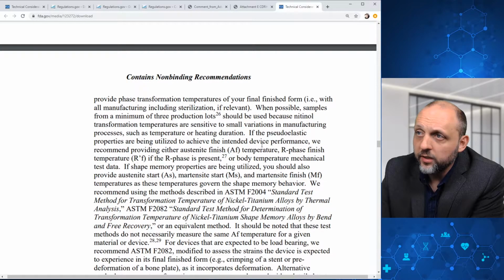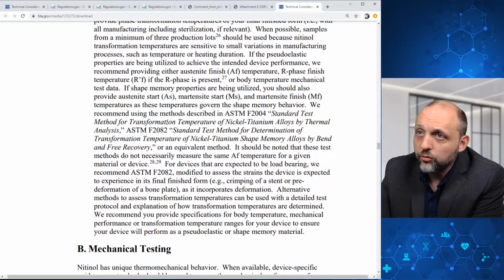Here, FDA gives some more details on what you should be doing if the pseudoelastic properties are being utilized to achieve the intended device performance. FDA also recommends using the methods described in ASTM F2004 and ASTM F2082 or an equivalent method.